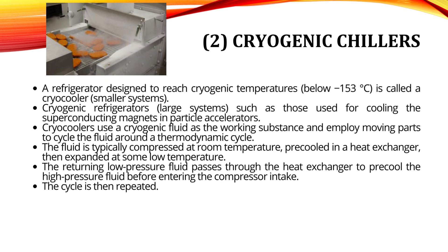A refrigerator designed to reach cryogenic temperatures is called a cryocooler. Cryogenic refrigerators are used for cooling superconducting magnets in particle accelerators. Cryocoolers use a cryogenic fluid as the working substance and employ moving parts to cycle the fluid around a thermodynamic cycle. The fluid is typically compressed at room temperature, pre-cooled in a heat exchanger, then expanded at low temperature. The returning low-pressure fluid passes through the heat exchanger to pre-cool the high-pressure fluid before entering the compressor intake, and the cycle is then repeated.